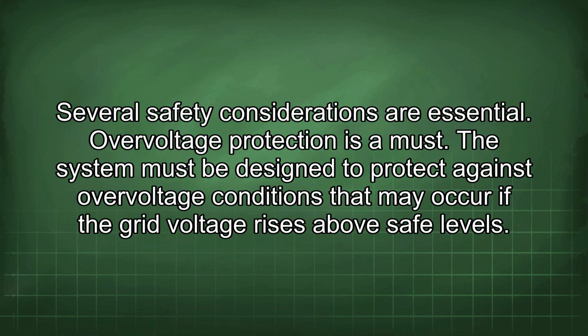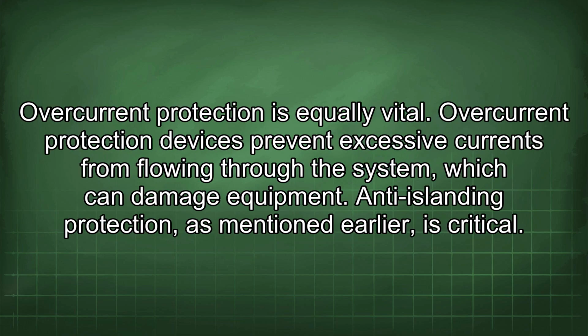Several safety considerations are essential. Overvoltage protection is a must. The system must be designed to protect against overvoltage conditions that may occur if the grid voltage rises above safe levels. Overcurrent protection is equally vital. Overcurrent protection devices prevent excessive currents from flowing through the system, which can damage equipment.